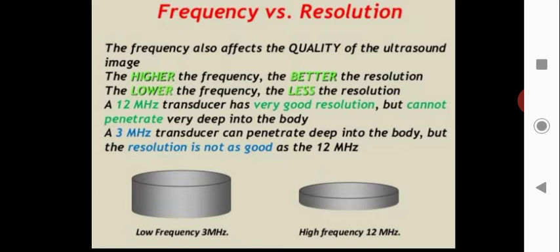Higher frequency gives better resolution — you get a clearer image. Lower frequency gives lesser resolution. At 12 MHz, the transducer has very good resolution but cannot penetrate very deeply into the body. At 3 MHz, the transducer can penetrate deep into the body but the resolution is not as good. Frequency and resolution are directly proportional, but higher frequency cannot penetrate as deeply into the body.